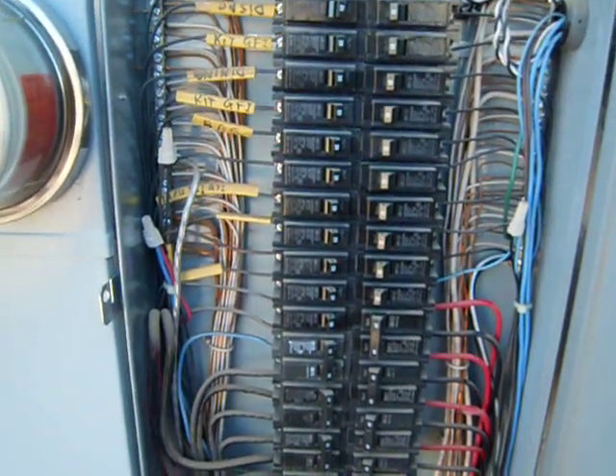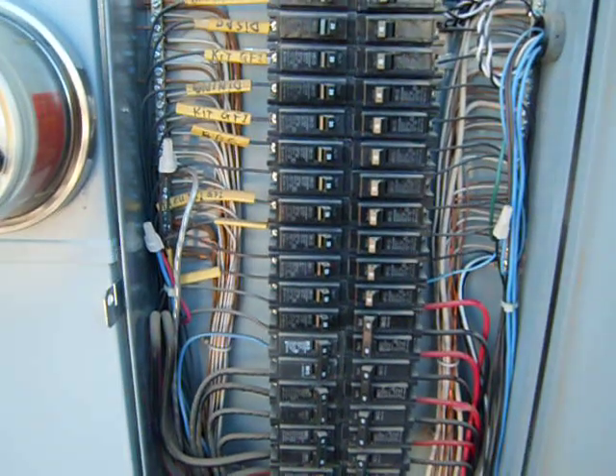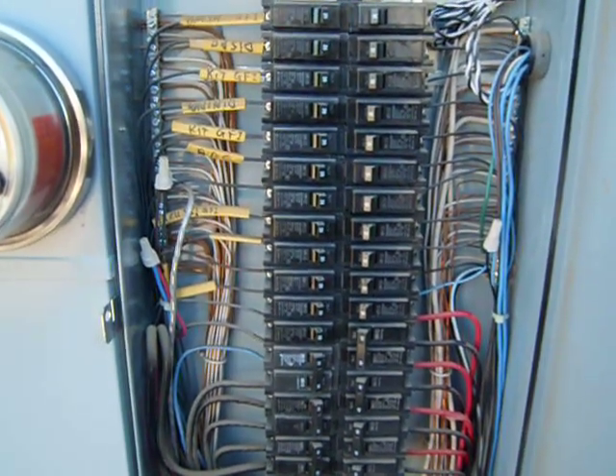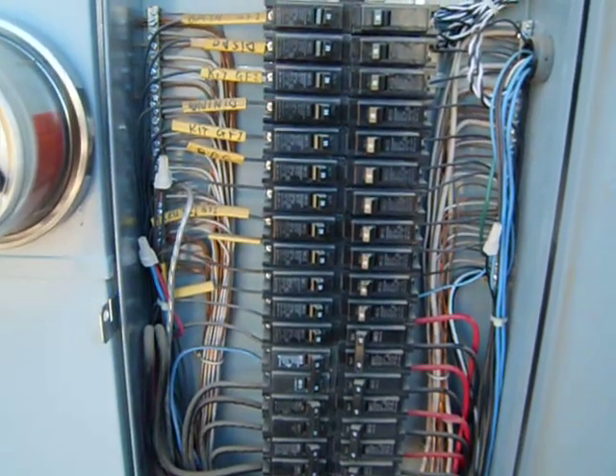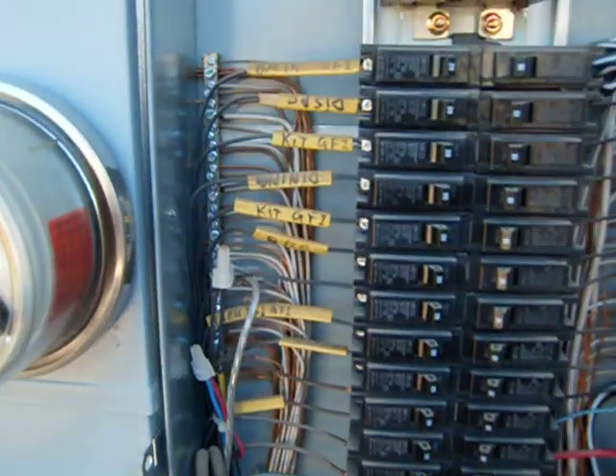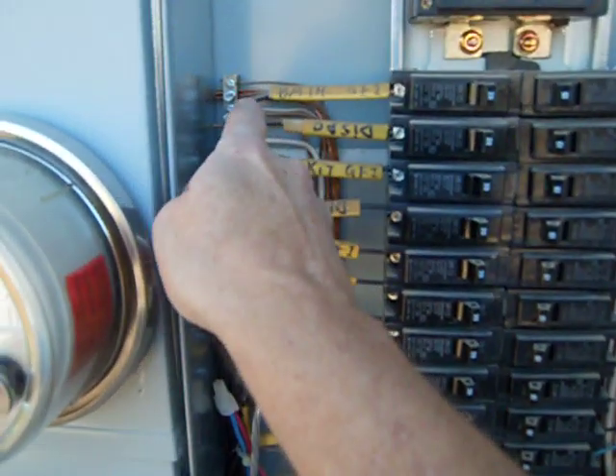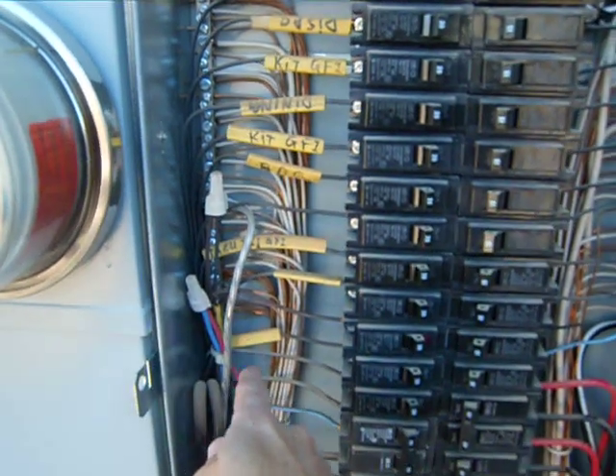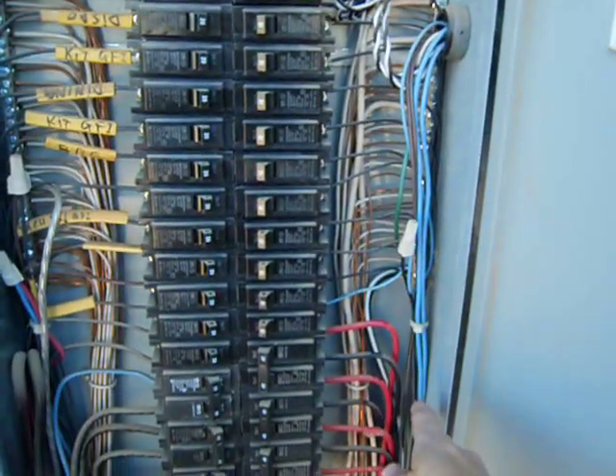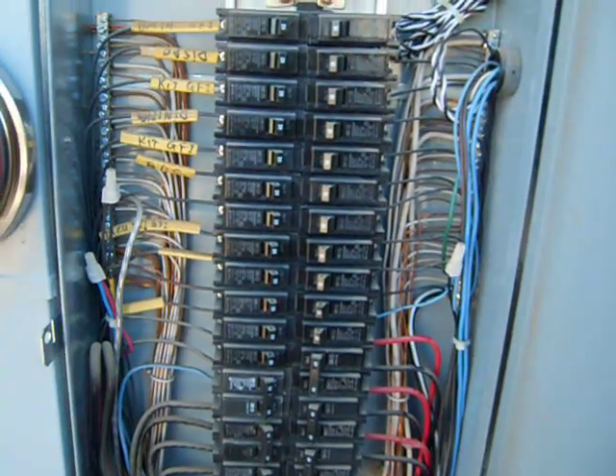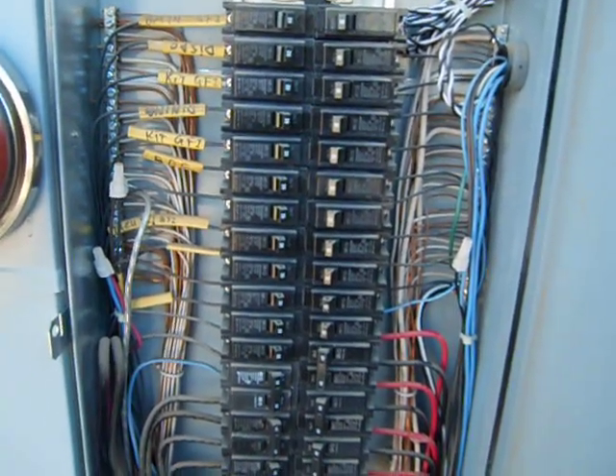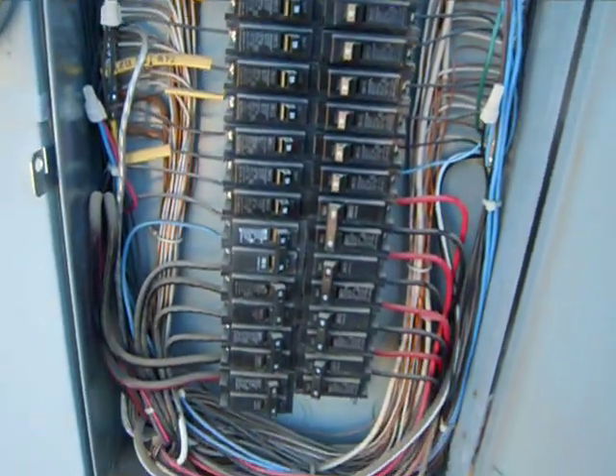You're going to see a lot of white wires in there. Those are your neutrals. And then you're going to see a lot of bare copper wires. And those are your ground wires. The neutrals and the ground wires all come together on the same electrical connection point in your panel. In my case, it's on both sides. So electrically, they're connected to the same point in the system, even though the wiring's separate in the house.